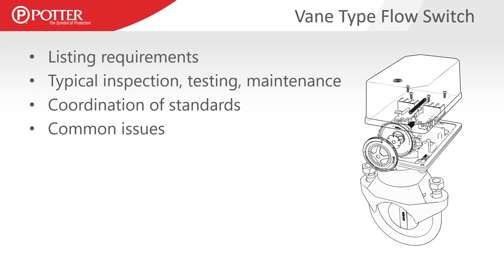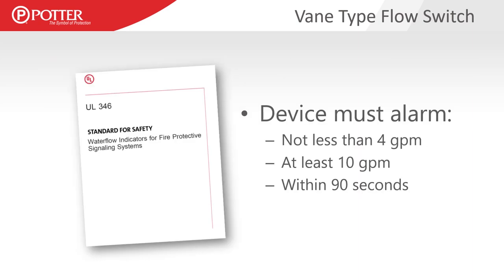We'll do this for each category of devices as we go through. This is the typical flow for vane type flow switches, pressure switches, tamper switches, and then a couple of other devices that supervise or monitor sprinkler systems. Regarding listing requirements for a vane type flow switch — it's important to understand how these devices must operate to meet UL listing, the UL 346 listing for water flow indicators.